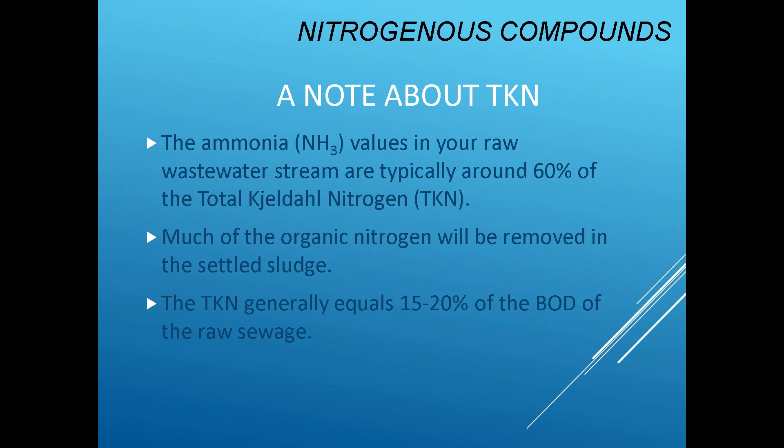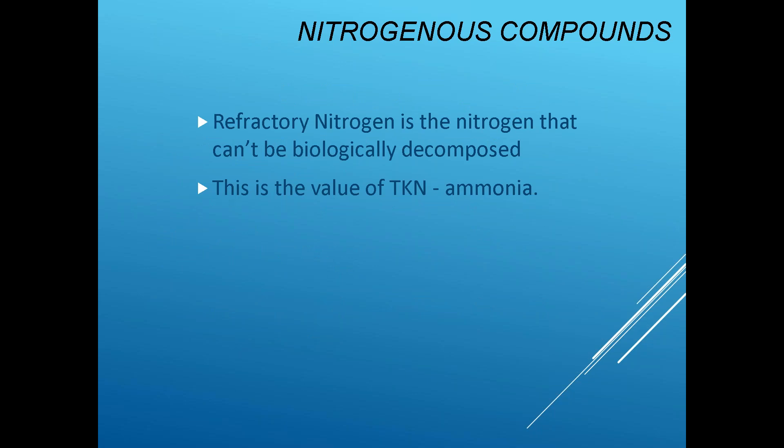If you only sample for ammonia in your raw waste, that's about 60% of the total Kjeldahl nitrogen. Much of the organic nitrogen will be removed in the settled sludge, and TKN is about 15 to 20% of the BOD of raw sewage. When designing for nitrogen removal, TKN should be your starting point. There is also some portion of TKN — refractory nitrogen — that cannot be biologically decomposed. It's a very old form of nitrogen that would take a huge effort to break, which is why some states use ammonia plus nitrate and nitrite rather than TKN.